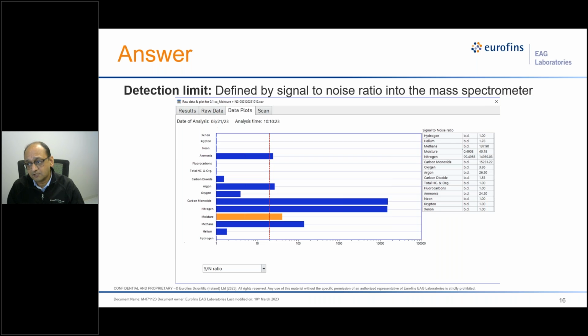Now this is also a part of our data processing software, and here I'm showing an example of the moisture calibration that was done yesterday. As you can see, these are the different gases being measured in the mass spectrometer. What we introduced is basically a mixture of nitrogen and moisture, as you can see in this table: 5000 ppm plus or minus 100 ppm moisture in a nitrogen mix. This was introduced to the mass spectrometer, and for moisture the signal to noise ratio is around 40, whereas for nitrogen it's very high because nitrogen is a very high signal here. And all other gases are below detection limit.